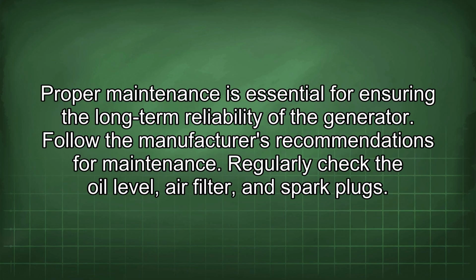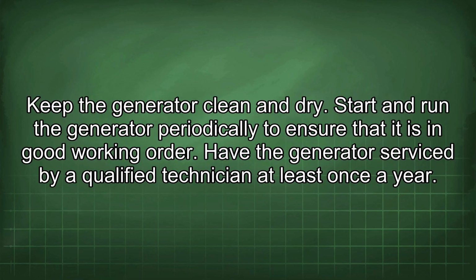Proper maintenance is essential for ensuring the long-term reliability of the generator. Follow the manufacturer's recommendations for maintenance. Regularly check the oil level, air filter, and spark plugs. Keep the generator clean and dry. Start and run the generator periodically to ensure that it is in good working order. Have the generator serviced by a qualified technician at least once a year.